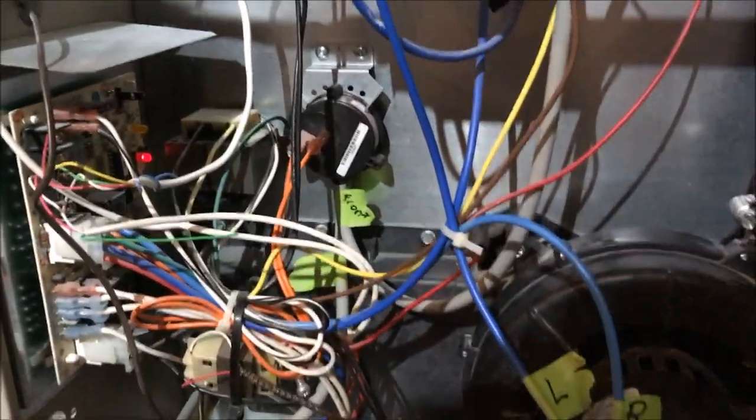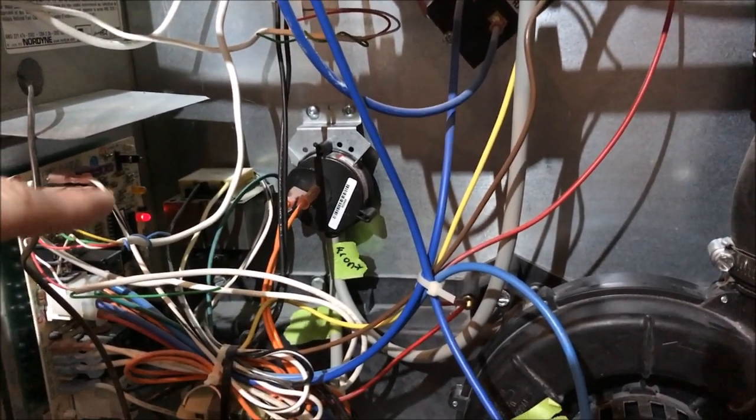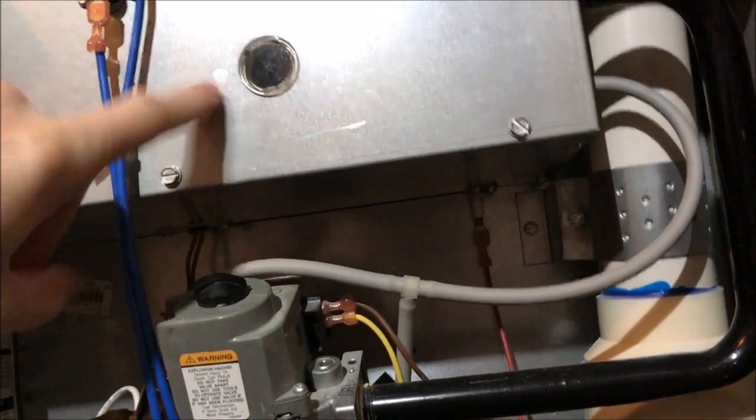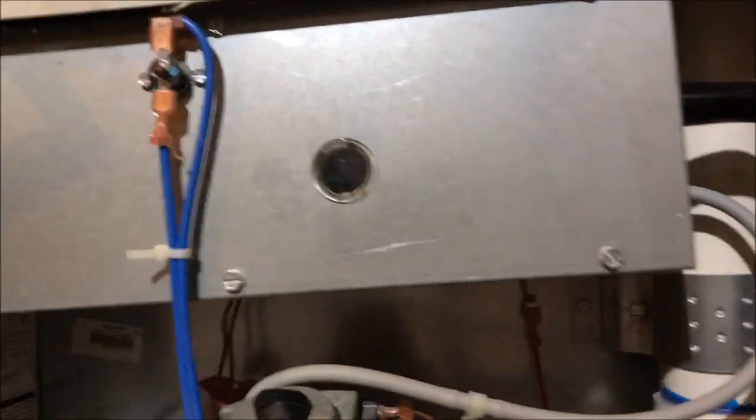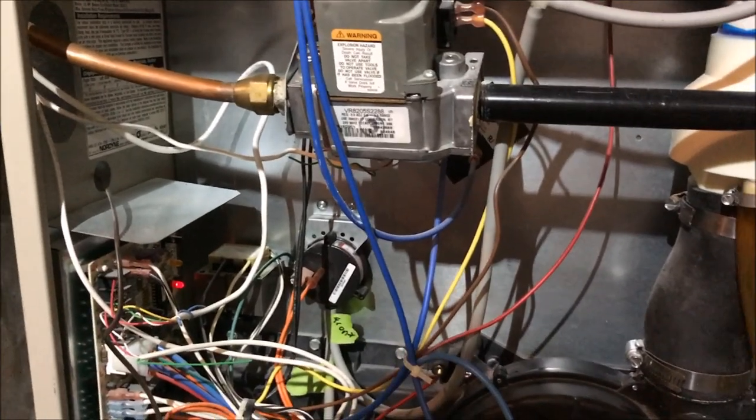Go ahead and click your furnace back on. Now if your furnace starts that light is going to remain red. It won't blink anymore. Red steady means everything's working fine. Also that yellow or amber light will also turn on steady once your heating element gets hot. Once you see a flame inside. If you kick it on and it works wonderful. You've more than likely solved your problem.